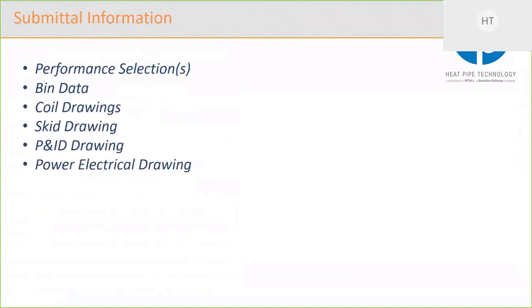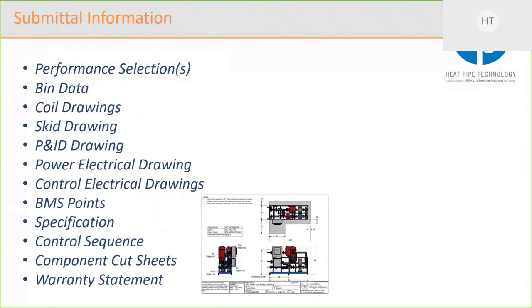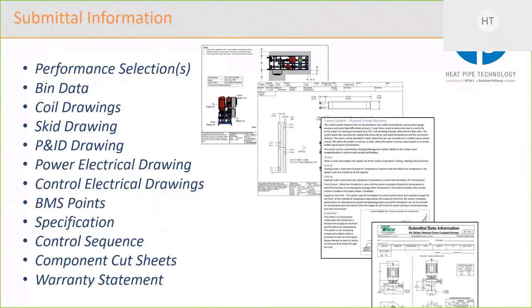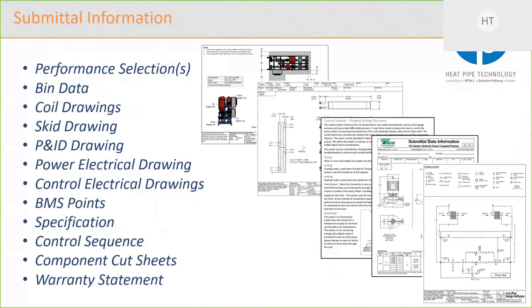So this slide really just shows you the sort of information you would get from a submittal from us. Again, the idea is this is pre-engineered, so we can give you pretty good submittal documents with comprehensive information quite quickly. The inputs you need to make a selection are very similar to a Heat Pipe. We are selecting it in the office right now with the applications engineers, so you do need to reach out to your local rep or directly to the office if you have an application. To get an initial selection, you would need the CFM, like airflow, the temperatures that the system is exposed to and what you're trying to achieve, and the geometry of the airflow, so height and length available for coil size.